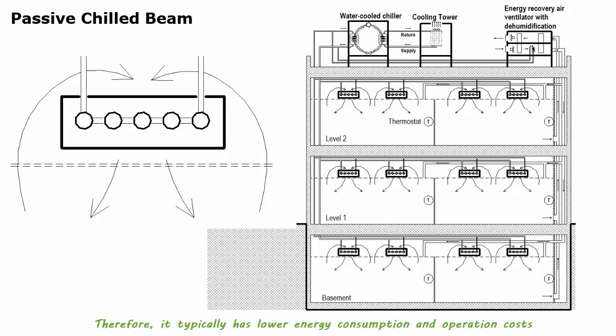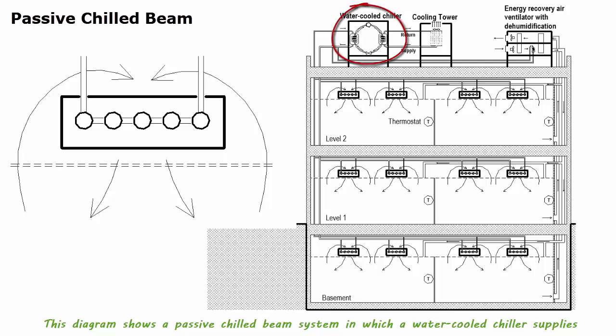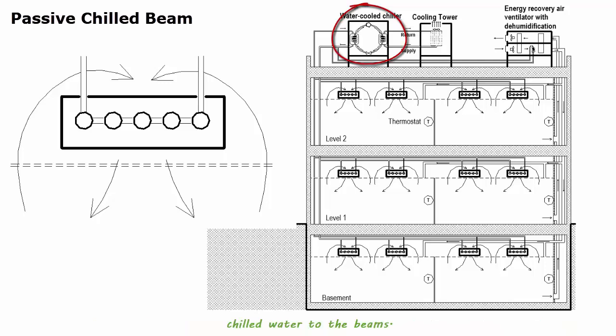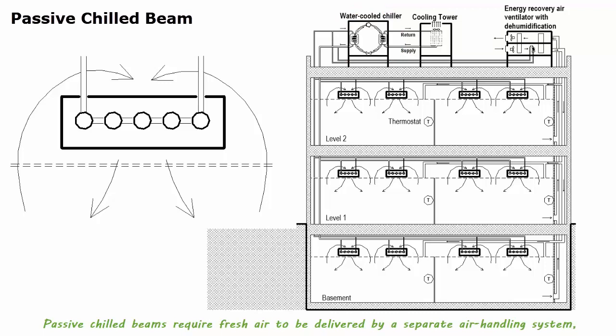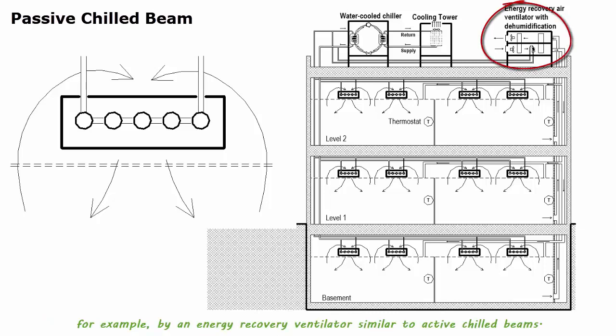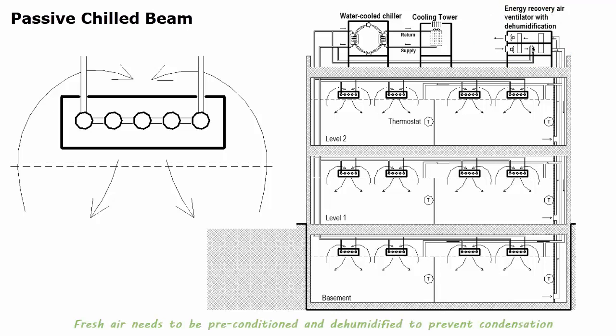Therefore, it typically has lower energy consumption and operation costs than the conventional all-air systems. This diagram shows a passive chill beam system in which a water-cooled chiller supplies chill water to the beams. Passive chill beams require fresh air to be delivered by a separate air handling system, for example, by an energy recovery ventilator similar to active chill beams. Fresh air needs to be preconditioned, dehumidified to prevent condensation forming on the heat exchanger.